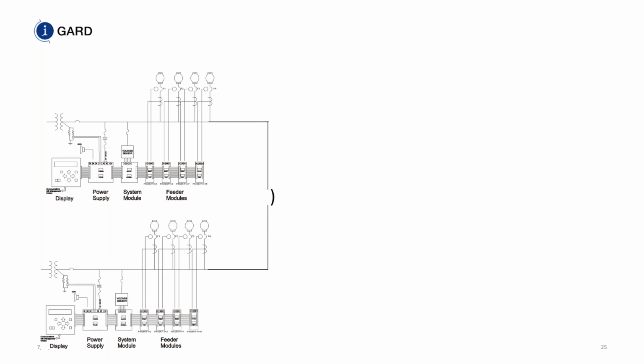And typically, the advanced HRG system can trip before the instantaneous protection of a circuit breaker. When the tie breaker is closed and you have one transformer feeding both sides, the communication goes across the tie breaker, and this can't be done with conventional relaying or PLCs. It could only be done with a dedicated relay.